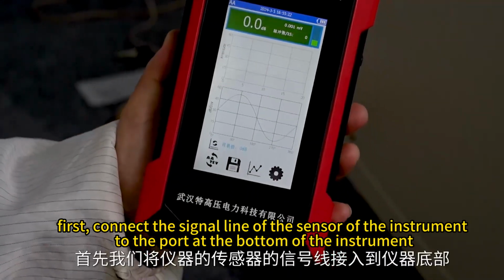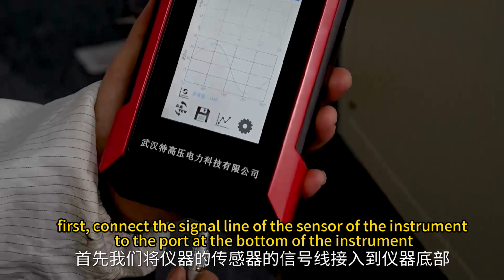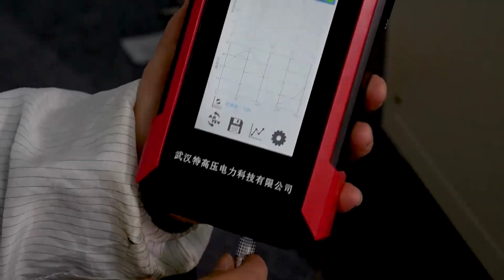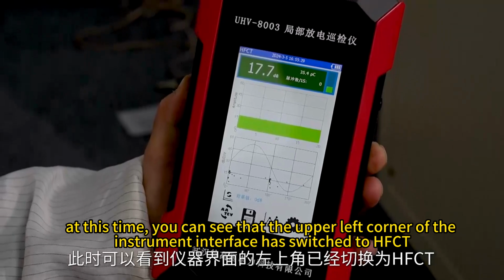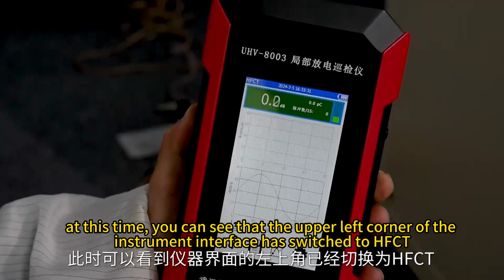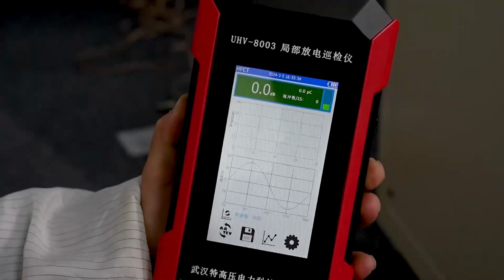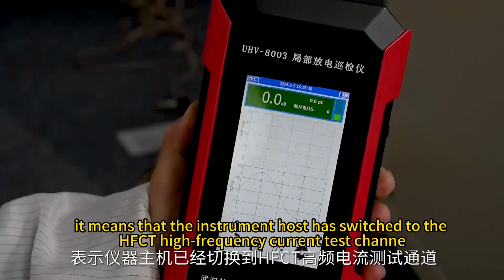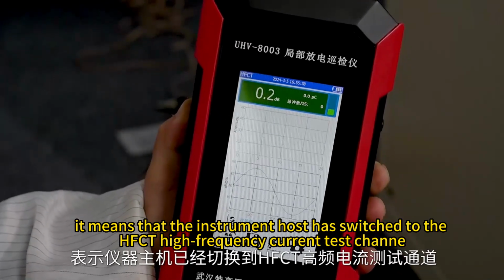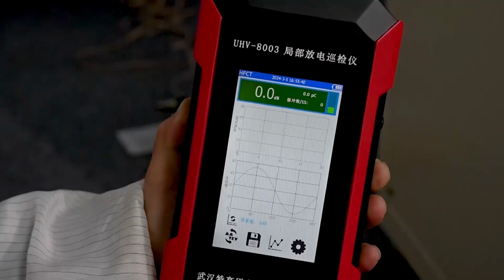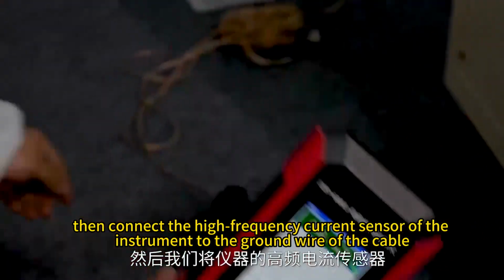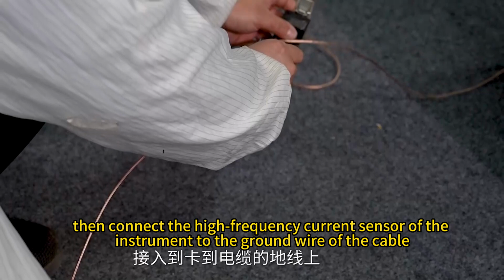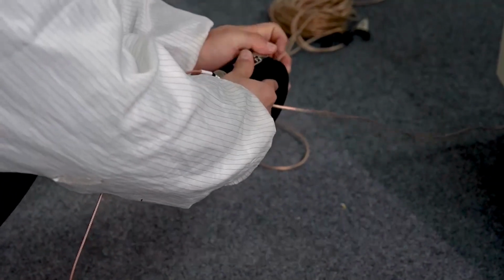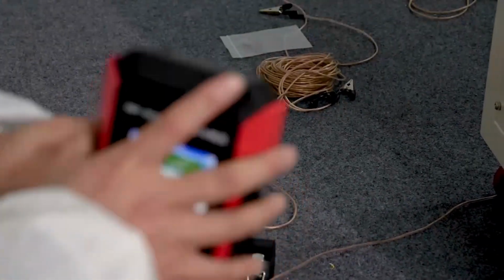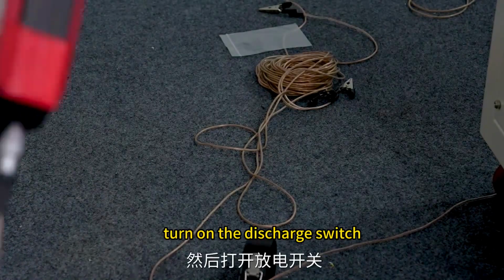First, connect the signal line of the sensor of the instrument to the port at the bottom of the instrument. At this time, you can see that the upper left corner of the instrument interface has switched to HFCT. It means that the instrument host has switched to the HFCT high-frequency current test channel. Then connect the high-frequency current sensor of the instrument to the ground wire of the cable. Turn on the discharge switch.